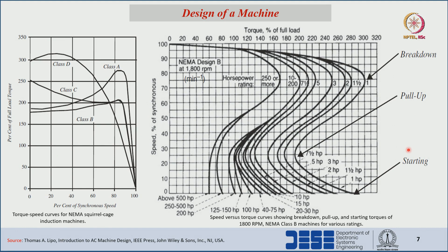Next, different NEMA design classes — class A, B, C, and D — are defined based on the percentage of full load torque for induction machines. Each class has different torque-speed characteristics. Class D provides the highest starting torque, so if a higher starting torque machine is required, we go with the class D type of design.